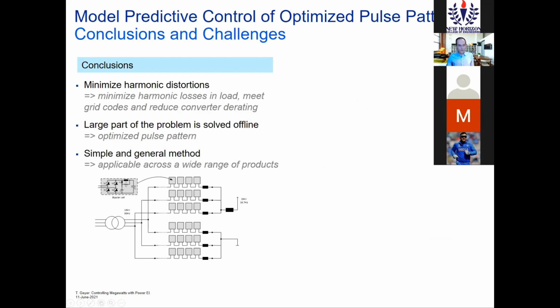So a few conclusions about MP3C, model predictive pulse pattern control. One is we minimize the harmonic distortions in the load. We can meet grid codes, harmonic grid codes. We can reduce converter derating, as you have seen. It is simple to solve online because the majority of the problem has been solved offline during a long weekend when we compute these optimized pulse patterns. And it's a simple and general method. So you can pretty much use it for most converters, particularly in the medium voltage domain.